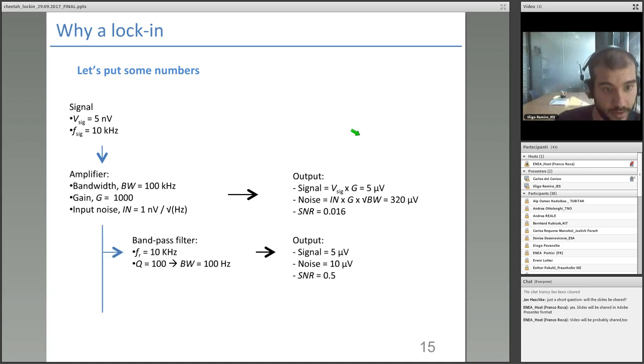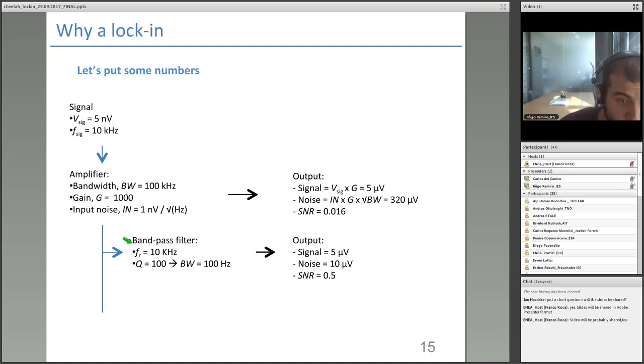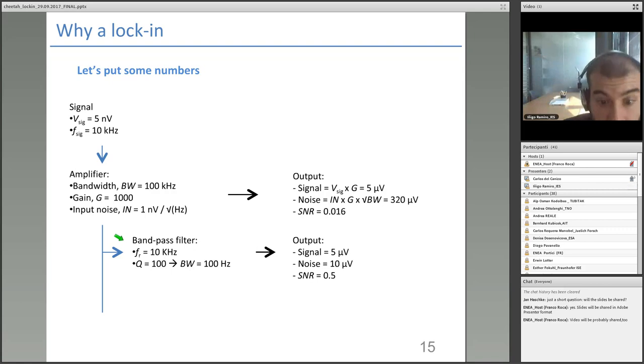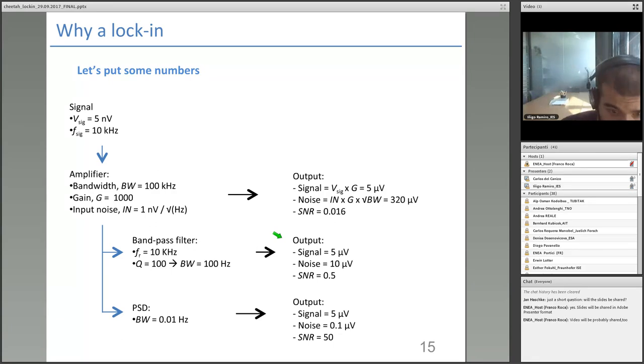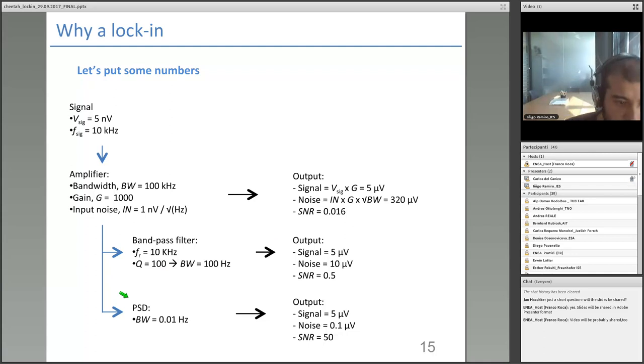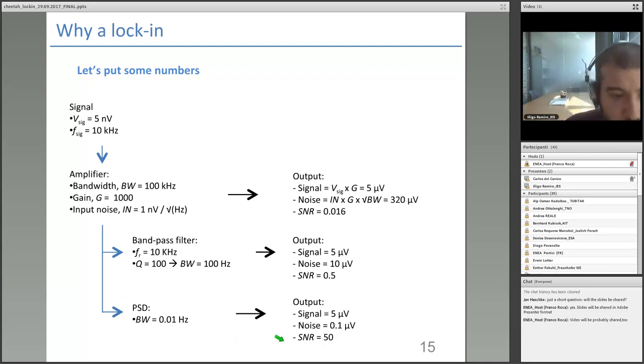Now let's say we add a very good bandpass filter at the output of the amplifier, centered at 10 kHz with a quality factor of 100. Doing the math gives a signal of 5 µV, noise of 10 µV, and an SNR of 0.5 — still a pretty noisy signal, difficult to measure accurately. If we use a PSD, we can narrow the transmission bandwidth down to 0.01 Hz or less. This yields an SNR of 50, which is 100 times better than with the bandpass filter, and we can now accurately measure our signal.